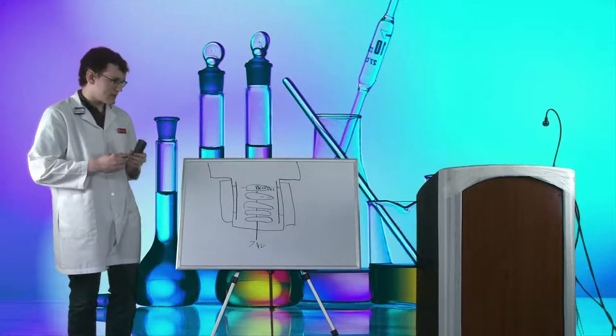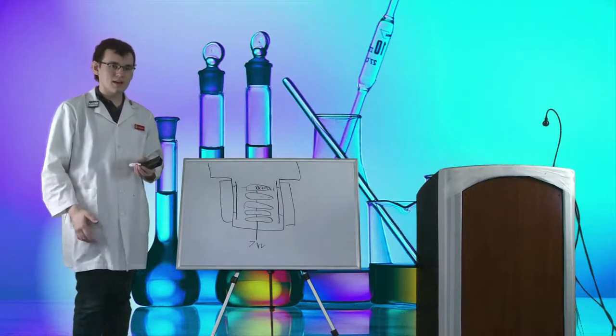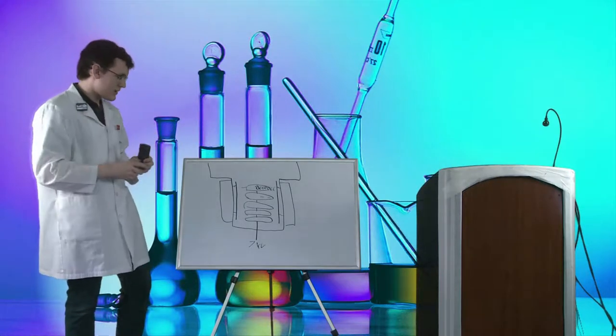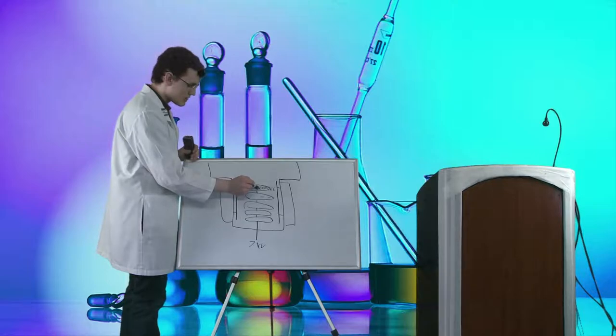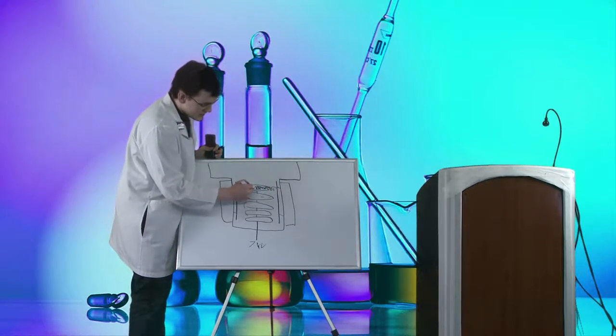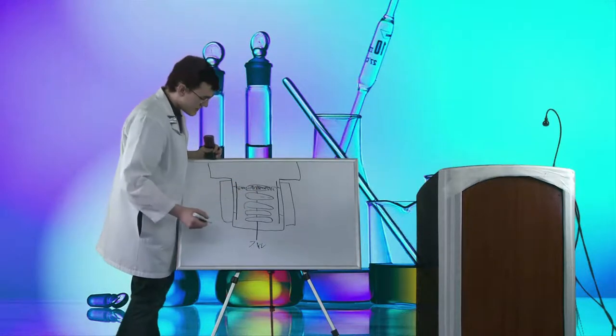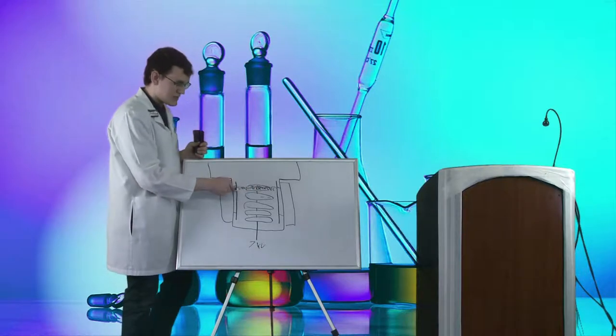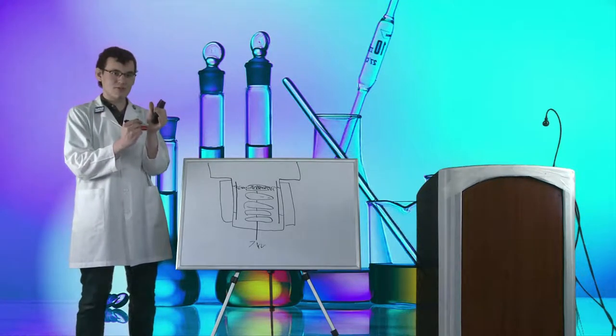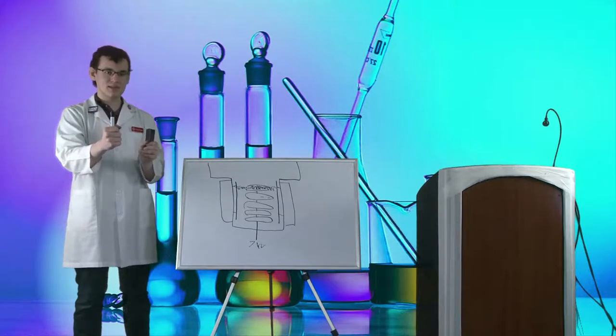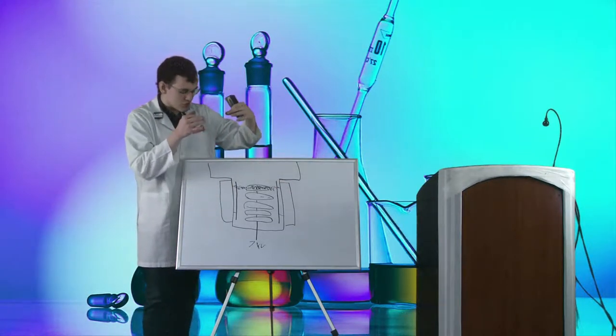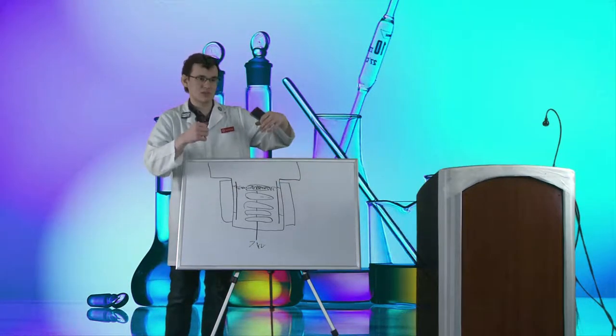We then slam these molecules into the titanium plates. Titanium is a relatively reactive metal, so the individual air molecules get slammed into the plates at such high velocity that they chemically react with the plates, getting stuck — thus being removed from the vacuum. There is no exhaust on this, and no roughing pump is needed. There's so little air at this point that we can just absorb the remaining molecules into the sheets of metal inside the pump. That's why it's called a getter pump — the metal is gathering up all these molecules.